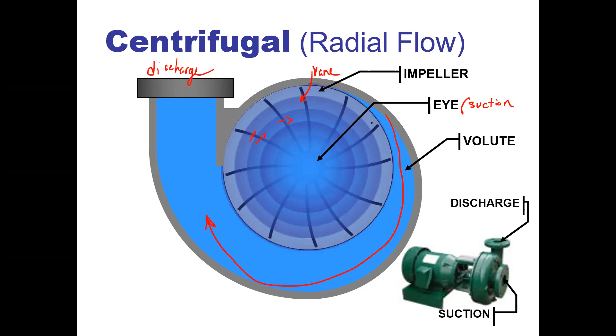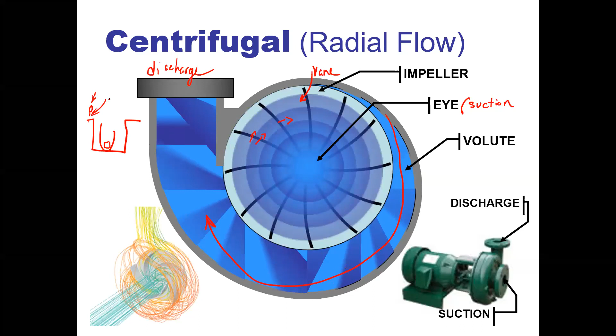No, what we actually did was just increase the pressure. Our valve was about a quarter of the way open, so what we did was open it all the way. We had a pressure gauge all the way up at the top of the dry dock. And what we did was disconnect the hose, and on our AC unit down in the little engine room, we rigged up another pressure gauge to see the actual pressure going in. We didn't run any calculations - we just added a pressure gauge, and we kept opening the valve up at the top of the dry dock in order to increase the pressure. You'll see why we just didn't add a pump in line: one, it would be highly annoying; two, we didn't have a pump to do it; and three, you'll soon see pump characteristics show why that really wouldn't work unless we had a full open valve here.